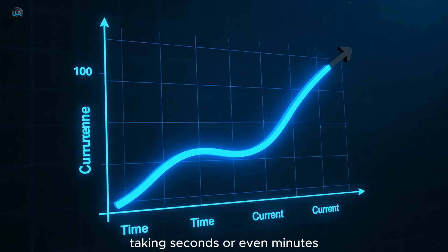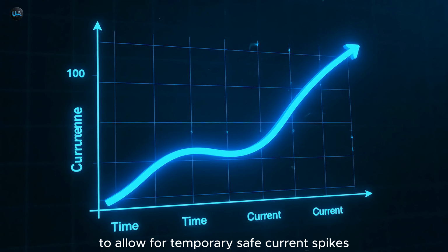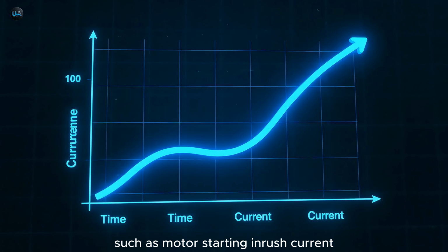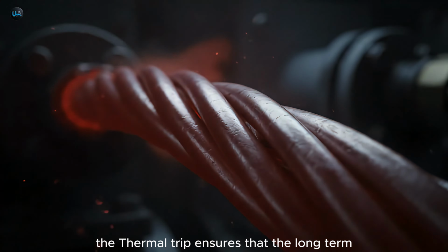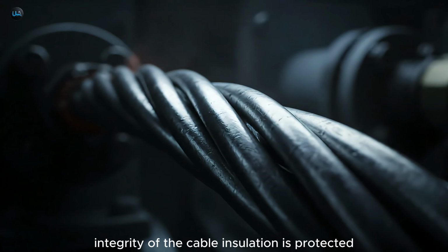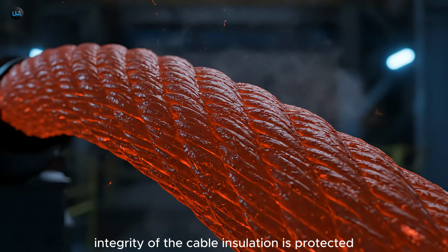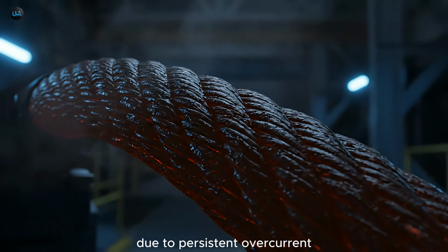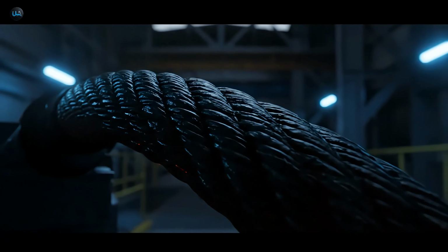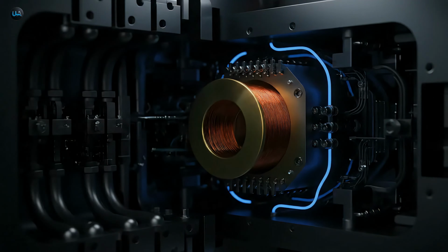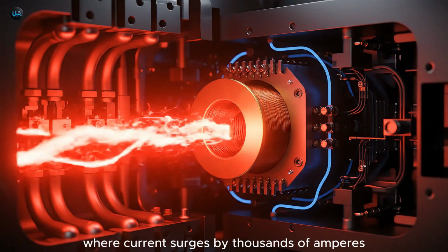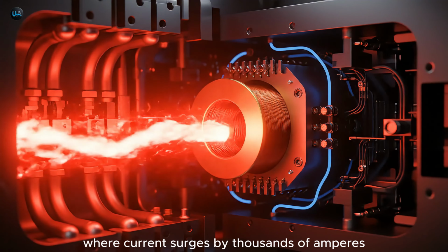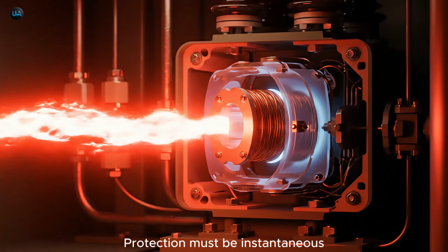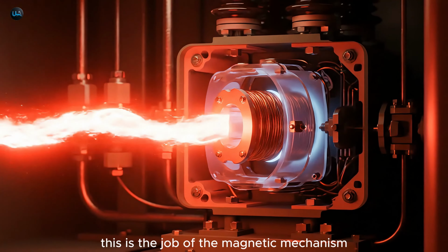This action is intentionally delayed, taking seconds or even minutes, to allow for temporary, safe current spikes, such as motor starting inrush current. The thermal trip ensures that the long-term integrity of the cable insulation is protected from heat damage due to persistent overcurrent. For a deadly short circuit where current surges by thousands of amperes, protection must be instantaneous. This is the job of the magnetic mechanism.